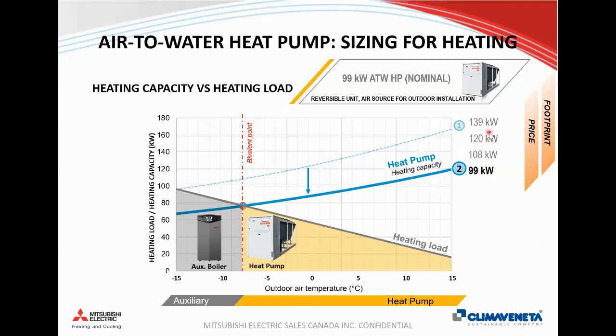But again, depending on if it's a retrofit, we'll most likely size this based off the cooling requirement and whatever heating we get out of the machine, and at what temperature we want to deliver it, and that will dictate our cutout temperature. But the main point here is that you can downsize the selection of the heat pump by considering that, because even if we design our system for our worst case design scenario, we really only see that for 1% of the time. So a lot of systems are oversized in terms of how they typically operate in normal circumstances.